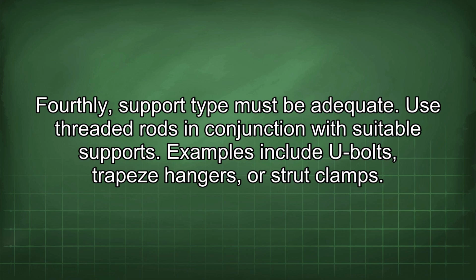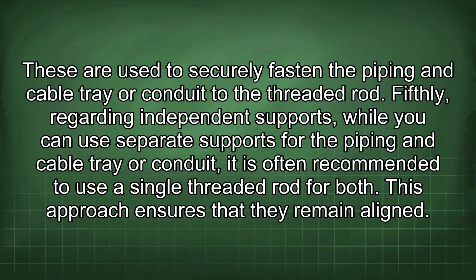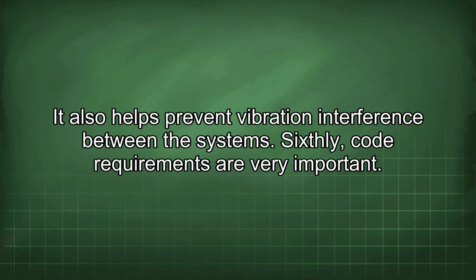Fourthly, support type must be adequate. Use threaded rods in conjunction with suitable supports. Examples include U-bolts, trapeze hangers, or strut clamps. These are used to securely fasten the piping and cable tray or conduit to the threaded rod. Fifthly, regarding independent supports, while you can use separate supports for the piping and cable tray or conduit, it is often recommended to use a single threaded rod for both. This approach ensures that they remain aligned. It also helps prevent vibration interference between the systems.